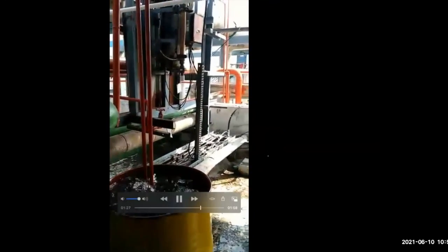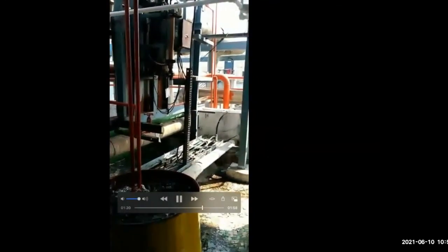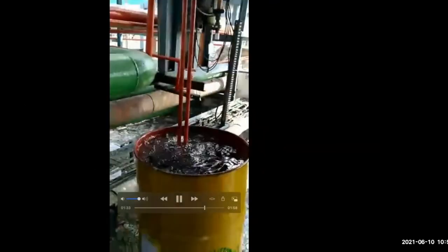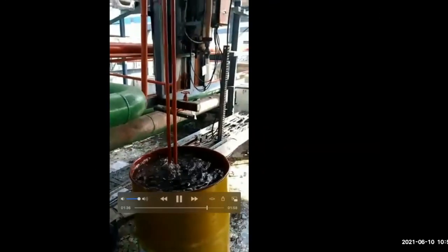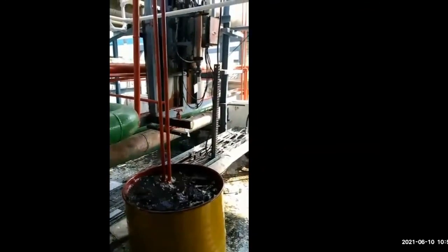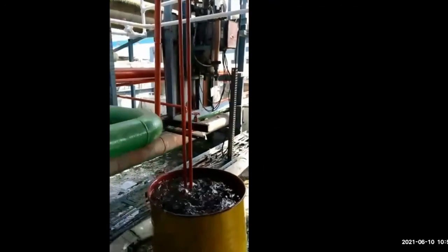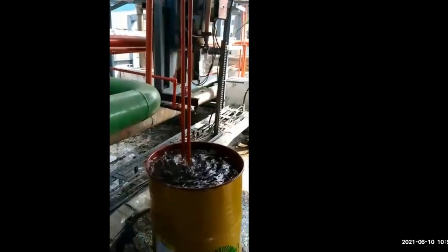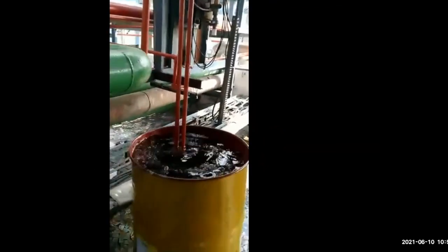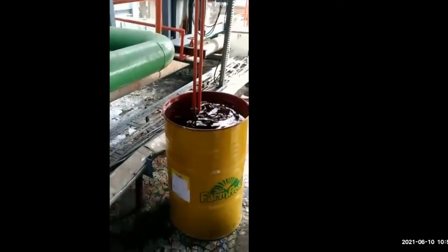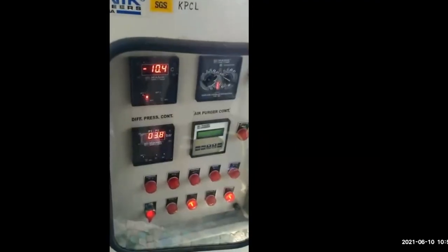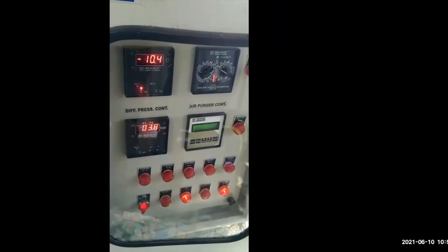It was quite a big plant. We have installed two automatic purger systems. The plant was at -40 evaporating and almost 1,000 tons of refrigeration capacity. So initially there was a lot of air being removed from it. This is the control unit for that purger. So that's all from today's presentation, sir.